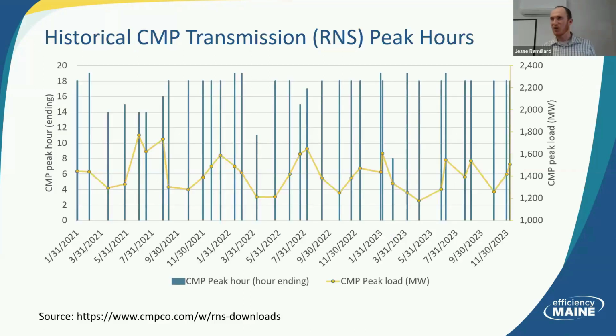Just exploring this a little bit further - you don't know when that peak hour is going to occur ahead of time. You won't know until the end of the month has gone by and you get your bill. So you have to predict, just like with the ICAP hour in the summer, when this hour is going to occur. Historically it has mostly occurred from 5 to 6 p.m. or 6 to 7 p.m. So CMP, the peak hour ending 18 or 19.